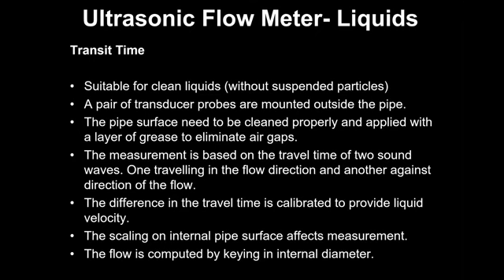This is an ultrasonic flow meter. This is a slightly tricky instrument because it has a slightly more complicated working principle, and there are 2 types available. One is for clean liquids. It is called a transit time type ultrasonic flow meter. Another is for dirty liquids. Dirty in a sense it contains either air bubbles or suspended solids. That is based on the Doppler effect, and the other is based on transit time.